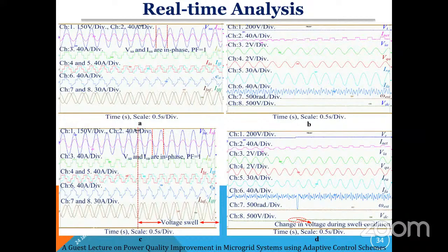And these are some internal characteristics of the controller. And see here, this is the second case, the voltage swell condition. And you can see the voltage swell condition. See the grid voltage and the DC voltage. In the normal condition, the voltage is maintained normal. When the grid voltage is increased, the DC voltage is also increased.